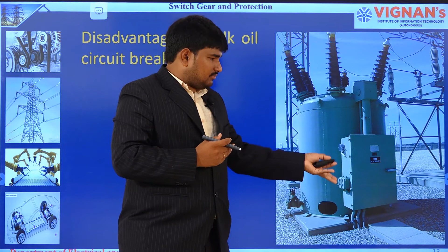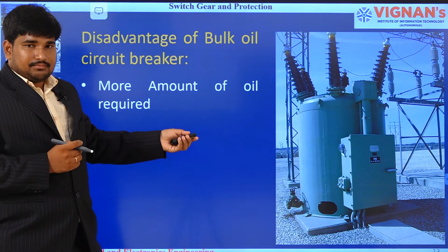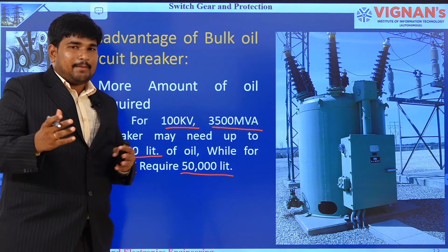Now let us come to the disadvantage part. What is the disadvantage of bulk oil circuit breaker? In bulk oil circuit breaker we need to have more oil. The name bulk oil indicates that only. More oil means more space, we need to have a big size. That is one disadvantage. And the second one is, for example, for a 100 kV, 3500 MVA circuit breaker, we need to have 10,000 liters of oil. If it is used for 220 kV, we need to have 50,000 liters. 50,000 liters indicates the amount of size we need to have for the tank. It is very big now.